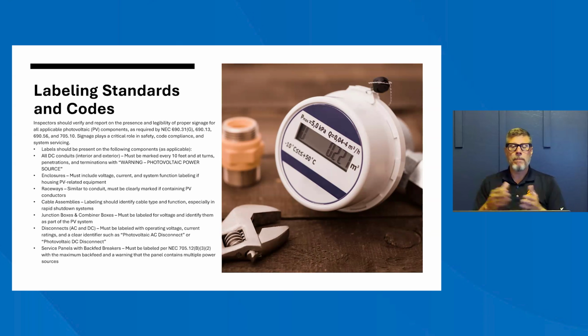Or at a maximum. They need to be at every turn, every bend, and at every wall penetration. They need to be on both ends of the array, and the lettering has to be 3/8 of an inch high and in all capital letters. The lettering has to be white reflective text, and it has to be on a red background. When you go to inspect these, they're going to be faded, they're going to be broken, they're going to be all over the place. So you want to make sure that you're paying attention to those, and we are calling them out.